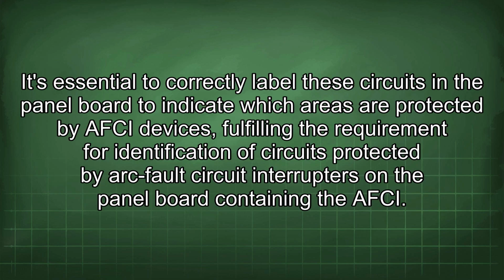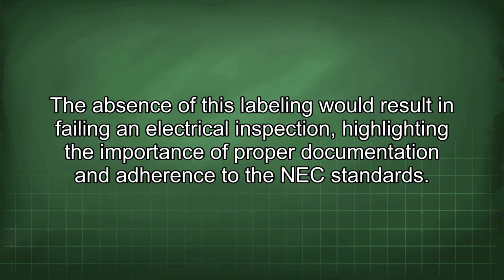It's essential to correctly label these circuits in the panel board to indicate which areas are protected by AFCI devices, fulfilling the requirement for identification of circuits protected by arc fault circuit interrupters on the panel board containing the AFCI. The absence of this labeling would result in failing an electrical inspection, highlighting the importance of proper documentation and adherence to the NEC standards.